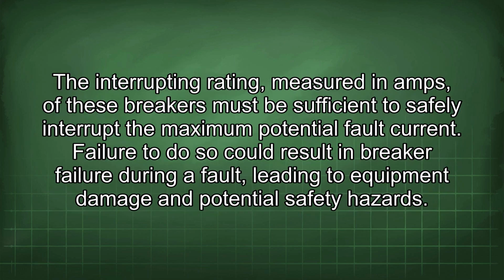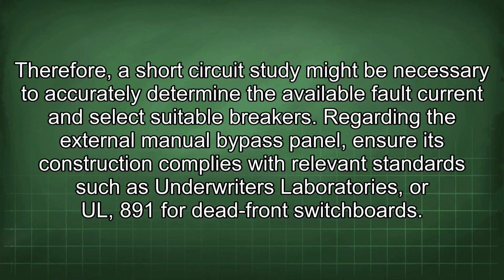The interrupting rating, measured in amps, of these breakers must be sufficient to safely interrupt the maximum potential fault current. Failure to do so could result in breaker failure during a fault, leading to equipment damage and potential safety hazards. Therefore, a short circuit study might be necessary to accurately determine the available fault current and select suitable breakers.